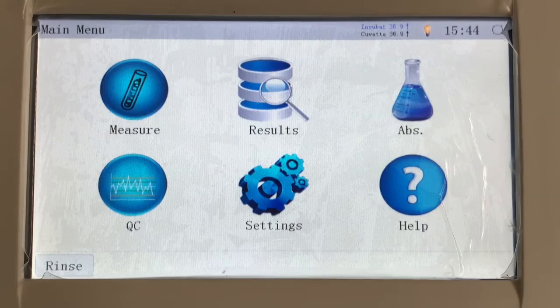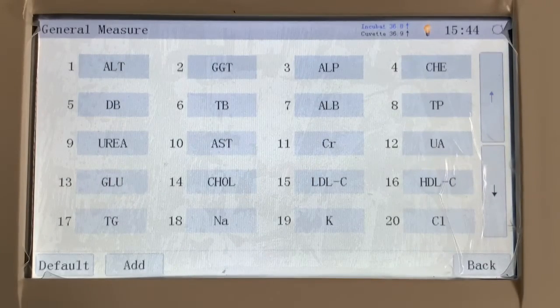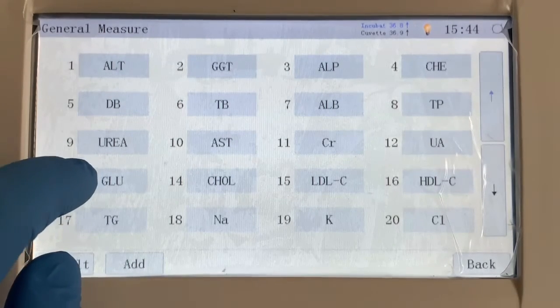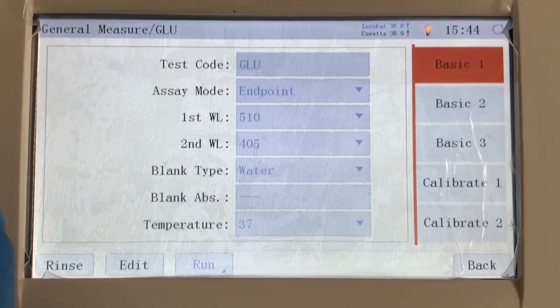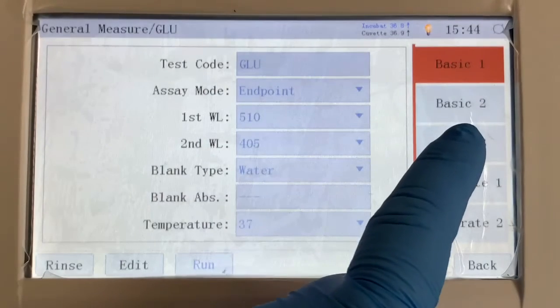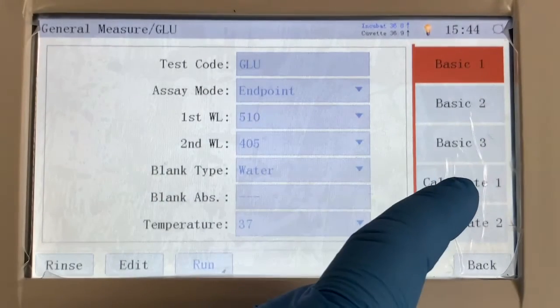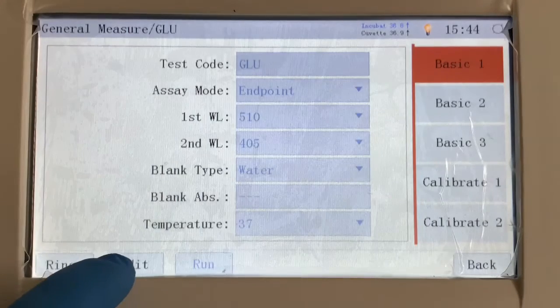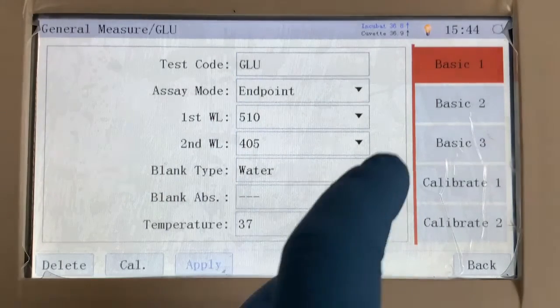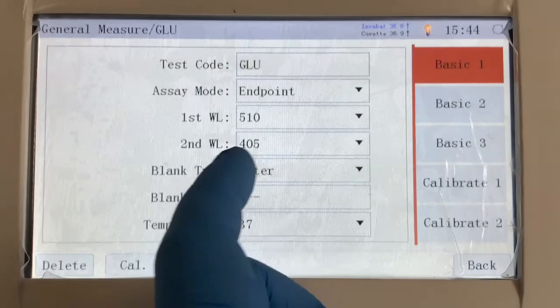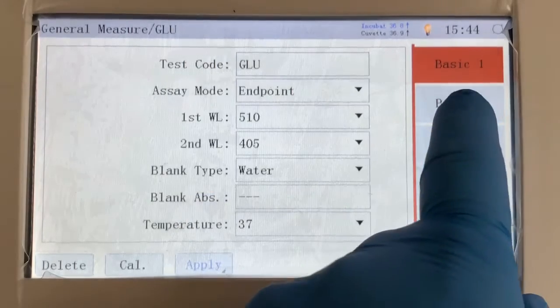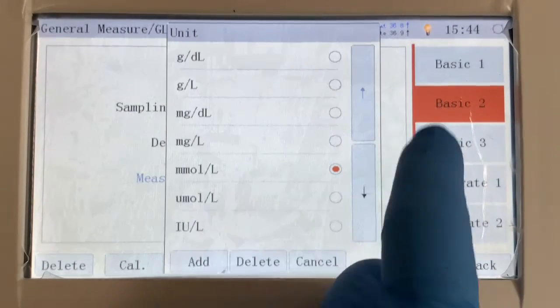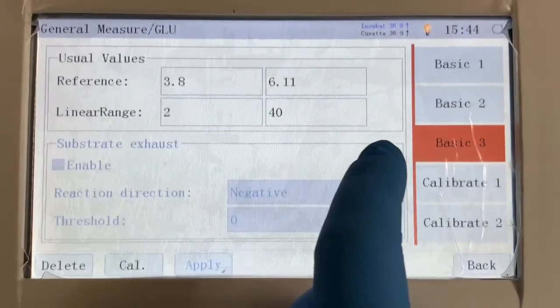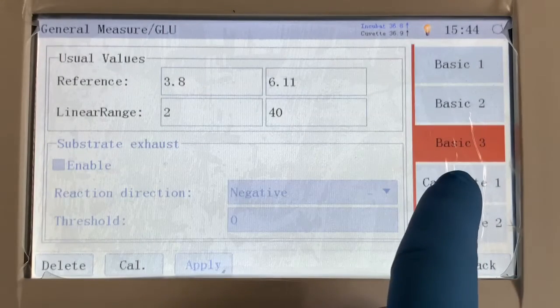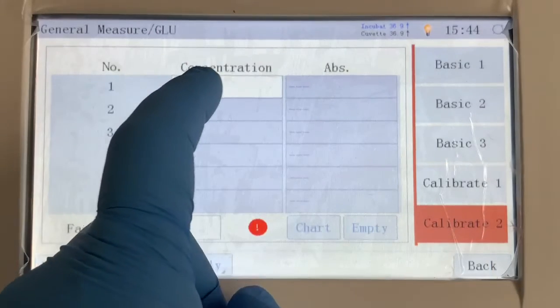Now we can do reagent protocol setting. In Measure, we can see there are factory preset test items. We take glucose, for example. We have 5 pages of setting, basic 1, 2, 3, and calibrate 1 and 2. Tap Edit. We can set parameters like blank type, unit, reference values, and calibration concentration.